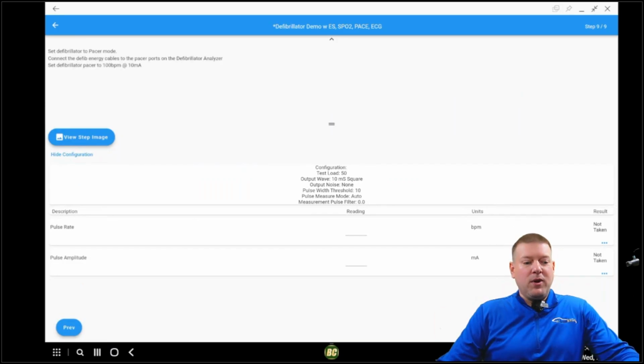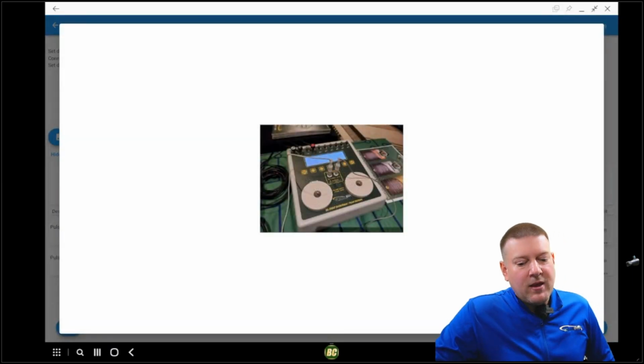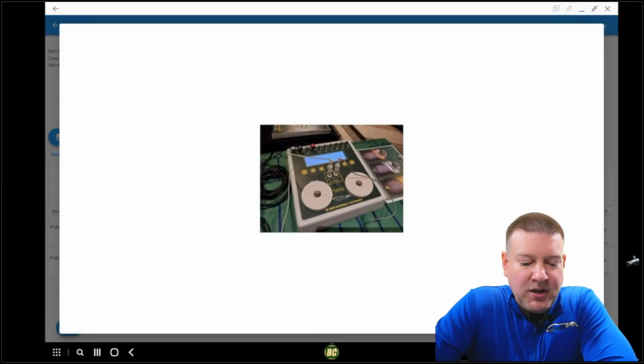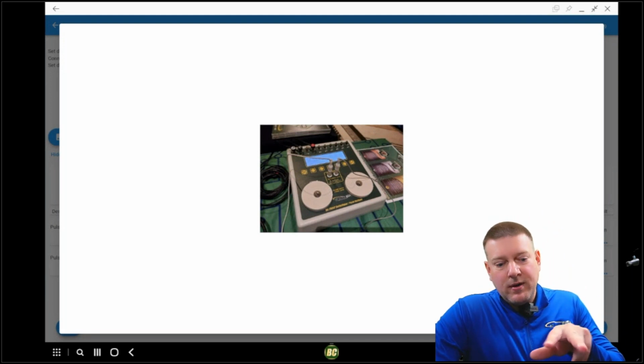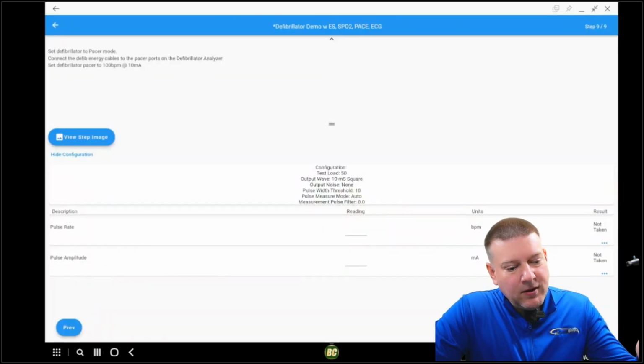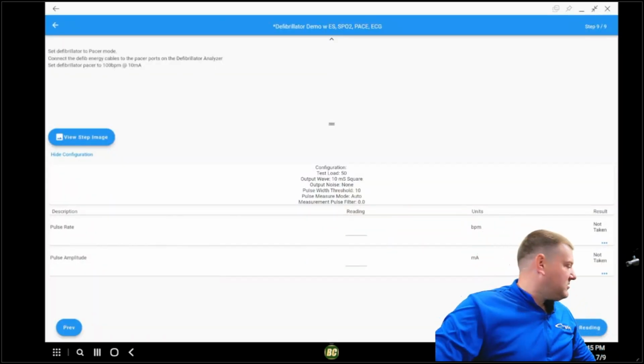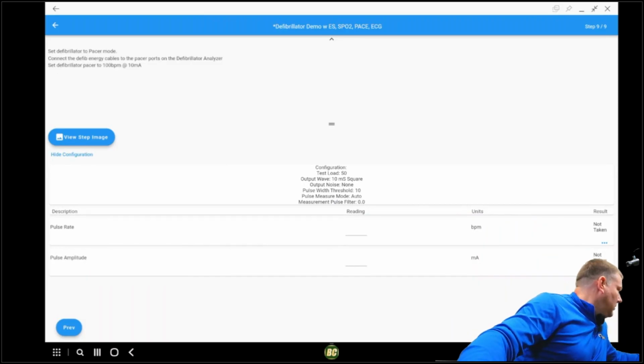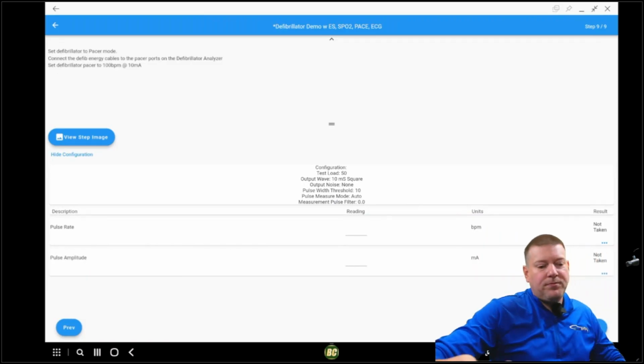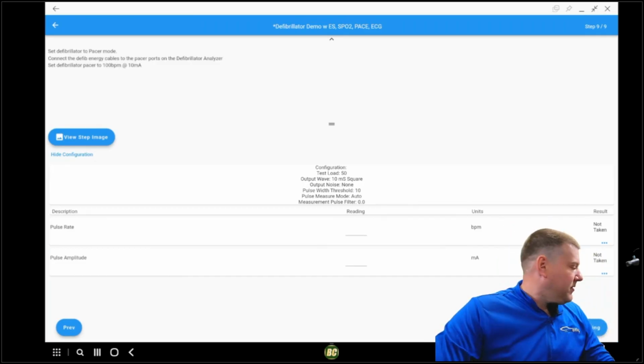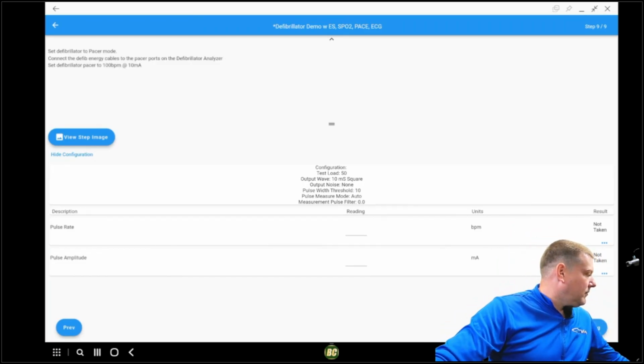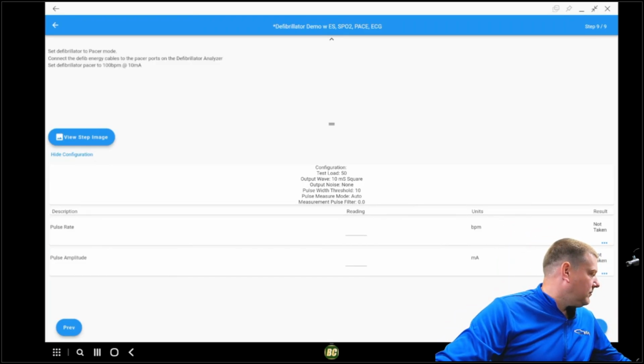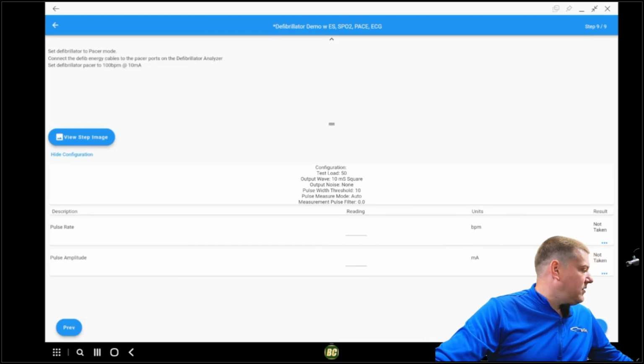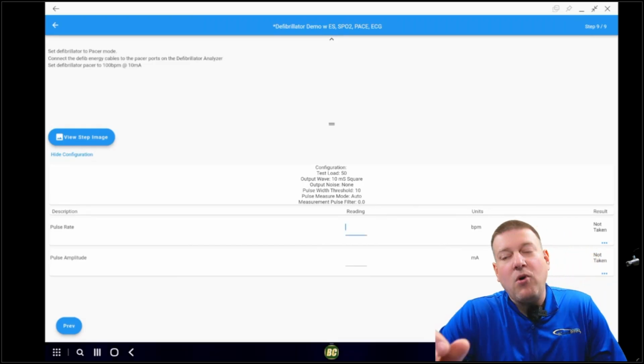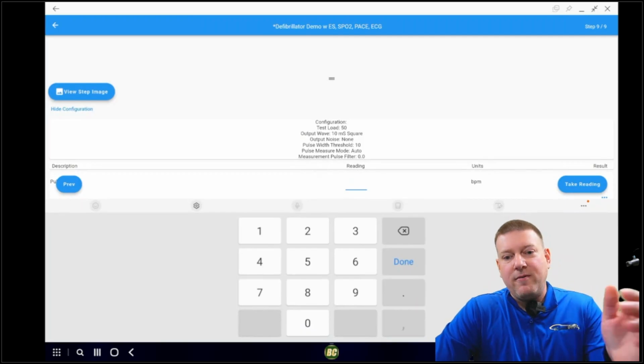And now we go into pacer. So we just follow the instructions. We move the pacing cables because we were on the defibrillator test ports. Now I tell them very specifically to connect the defib energy cables to the pacer ports. So we move the cables, and then it says to set the defib to pacer. We set the rate, and then we set the current, and it will automatically capture that.